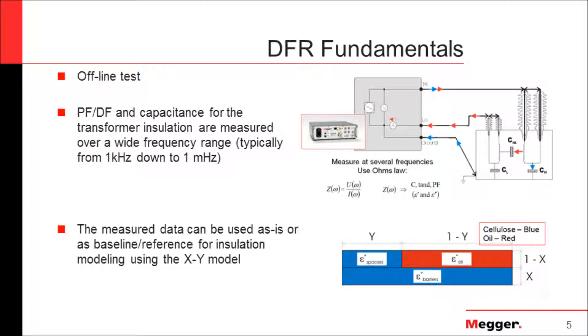The principle for power factor and dielectric frequency response is the same — we are measuring complex impedance. We have a reactive component and a resistive component representing the losses. From here we identify the cosine of angle theta, which represents the power factor. The difference is that in dielectric frequency response analysis, we run several power factor tests at different frequencies, going from high frequencies at about one kilohertz all the way down to one millihertz. Power factor testing is frequency dependent, so every time we change the frequency, we change the value of the capacitive reactance, the complex impedance, and the resulting power factor value.